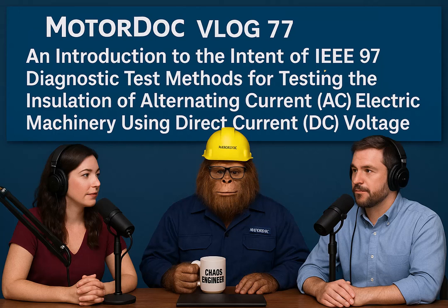Now, remember those current components we talked about? Yeah, capacitive, absorption, conduction. Under a ramp voltage, the capacitive current is actually constant because the rate of voltage change, dV/dt, is constant. Interesting. And the absorption current tends to follow the voltage pretty linearly. So if you see significant nonlinearity in the total measured current, the curve starts to bend upwards sharply, or it gets wavy, that often points to the conduction currents increasing, or maybe localized defects starting to become active as the voltage gets higher.